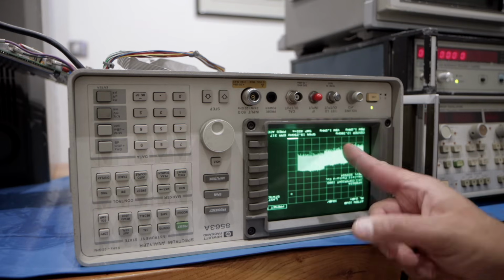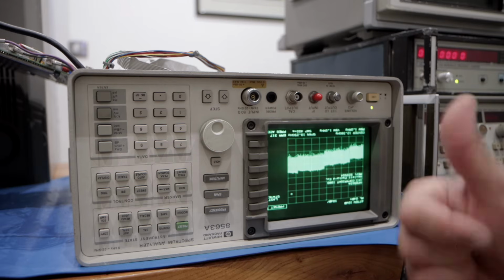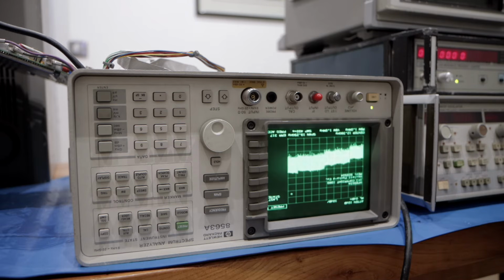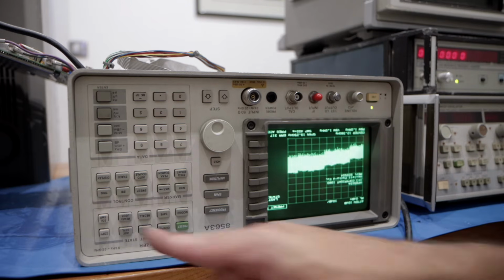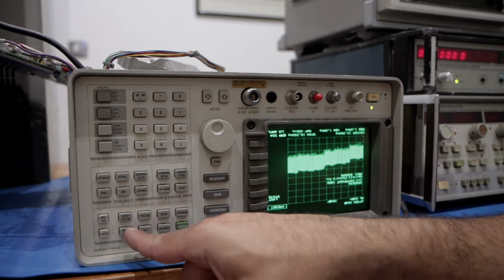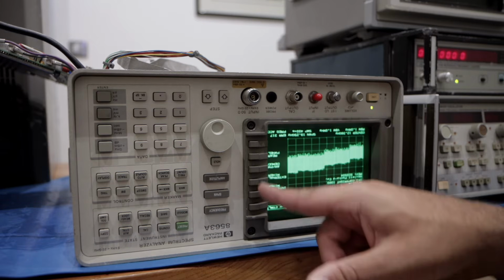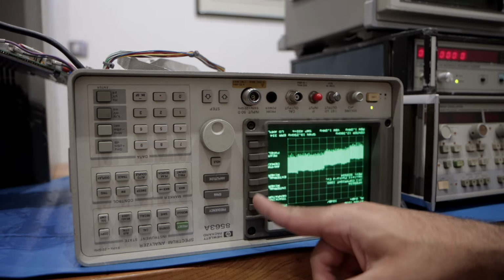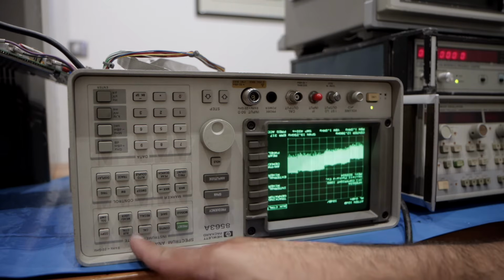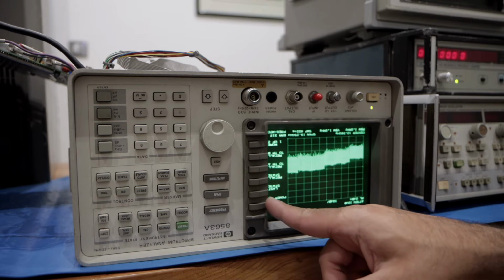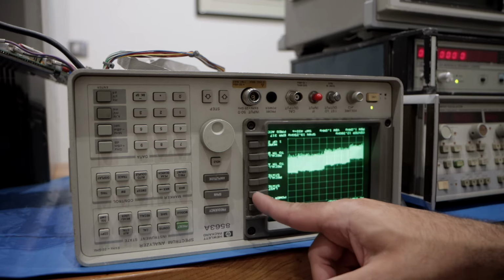The startup behavior is different from what I observed until now, and much faster. And this is a success. The typical noise floor of this harmonic mixing analyzer is back. I'm glad I found the issue, which is a dead oscillator. But honestly, I'm a bit disappointed. I was hoping the remaining parts in this instrument were still functional. Now I'm starting to doubt the other components too.